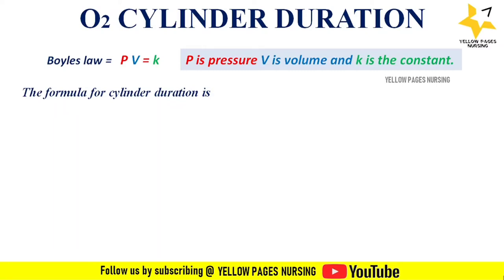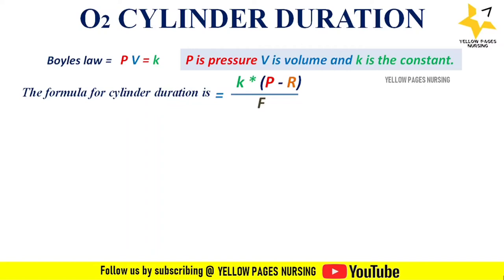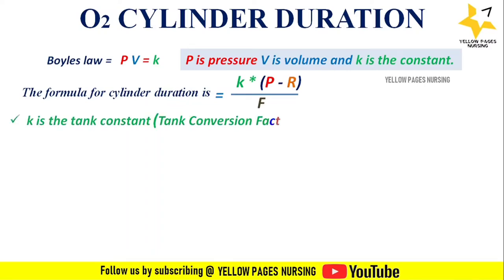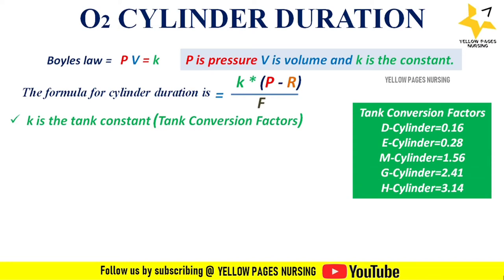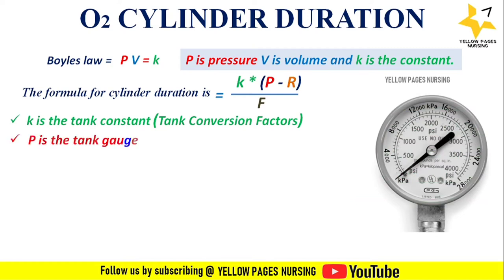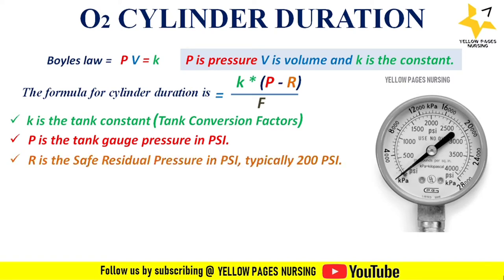The formula is: K multiplied by (P minus R), divided by F — where K is the tank constant or tank conversion factor. Each cylinder size has its own constant, as shown in the image. P is the tank gauge pressure in PSI (pounds per square inch), and R is the safe residual pressure in PSI, typically 200 PSI.